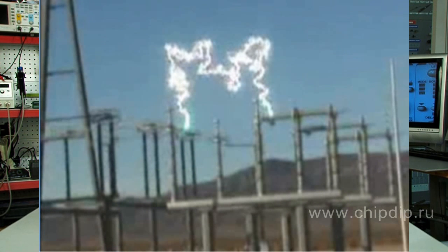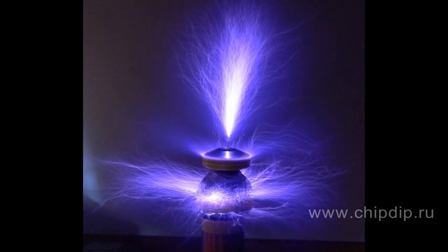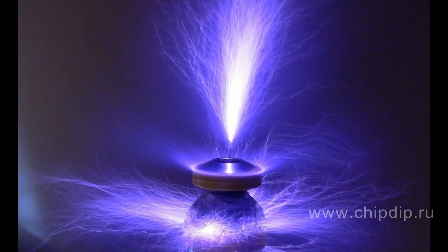In arc chutes with magnetic blasts made using permanent or electromagnets, the arc is drawn quickly into the chamber due to exposure to the magnetic field formed by these magnets. Arc quenching in air circuit breakers occurs due to the flow of compressed air. The design of air circuit breakers varies depending on the rated voltage.